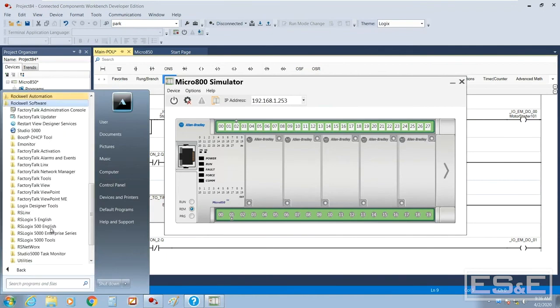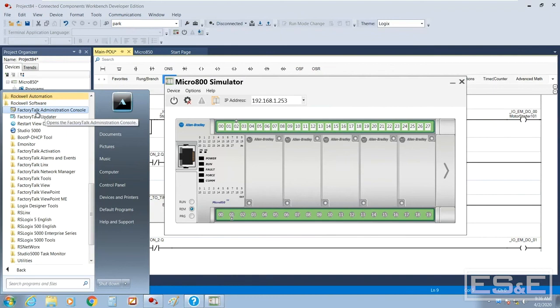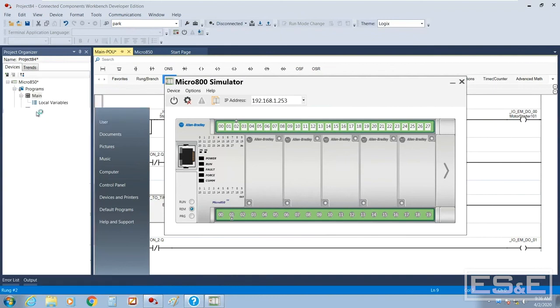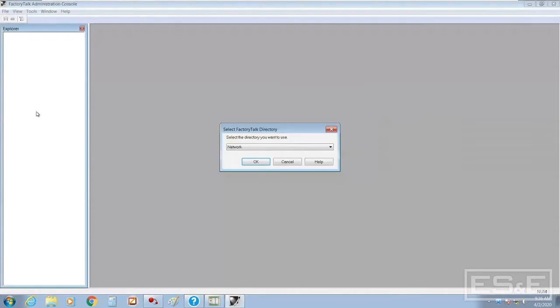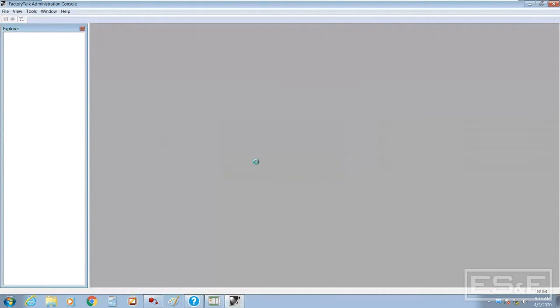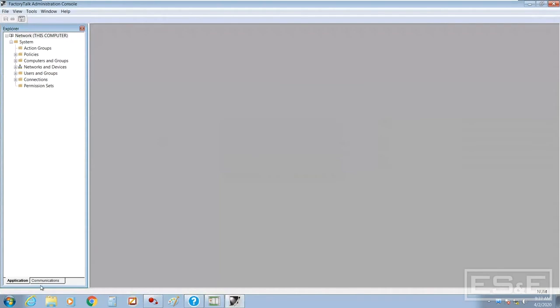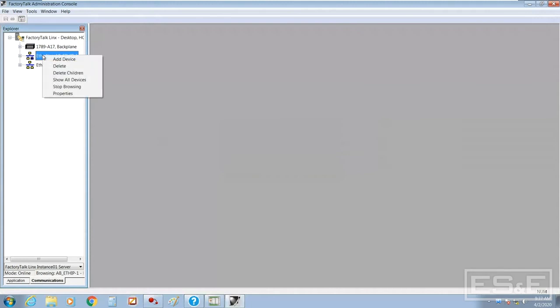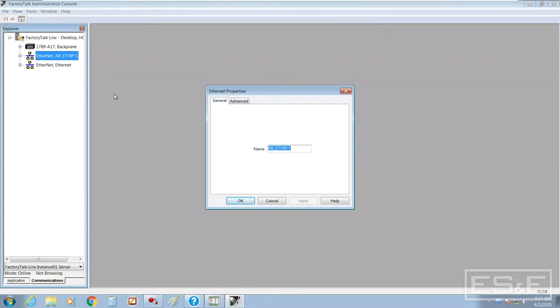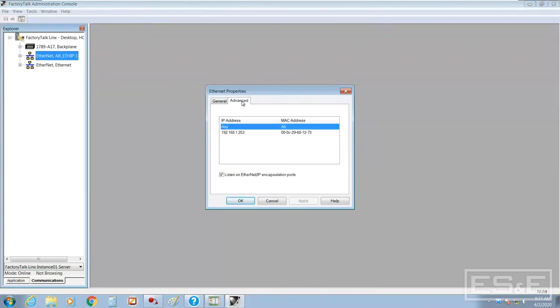Simply go to the FactoryTalk software folder. There is what's called the FactoryTalk admin console. You select network, and then you select the communications tab. We come over here and select the ethernet driver. I right mouse click on the ethernet driver, select properties. I select the advanced tab. And the only thing I have to do to fix that error is to uncheck listen on ethernet IP encapsulation ports.